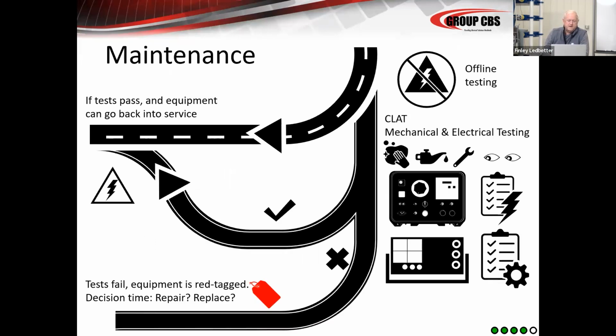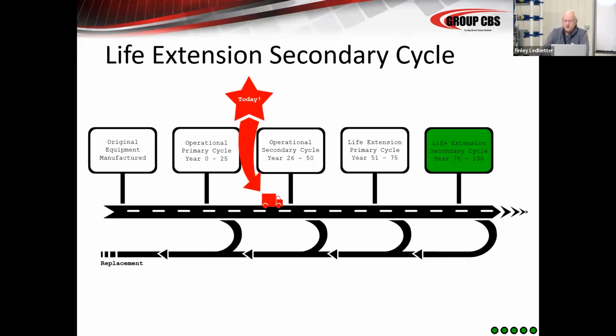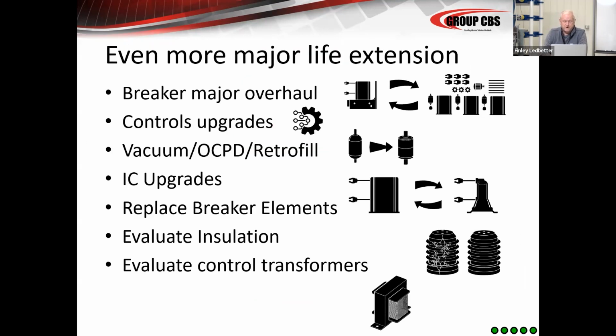There again, the same thing happens. The ones that fail go to red tag. They go out for repair or replace. It's decision time on this old equipment. The things that pass test and inspect are going to go right back on the racetrack for 5, 10, 15, 20, 25 more years. And then you're going to move on to your secondary life extension, or your 75 to 100 year cycle. Now, 100 years we thought was a long time, but here we are, we're there.